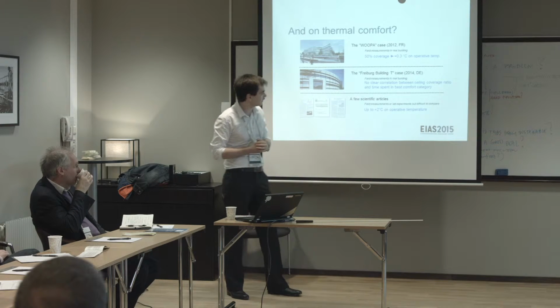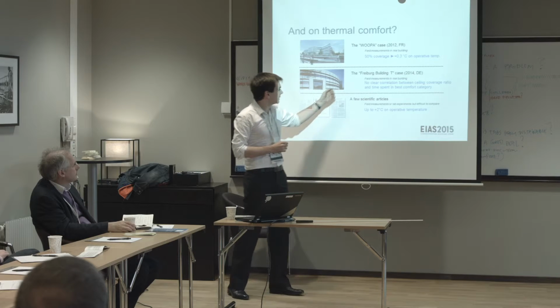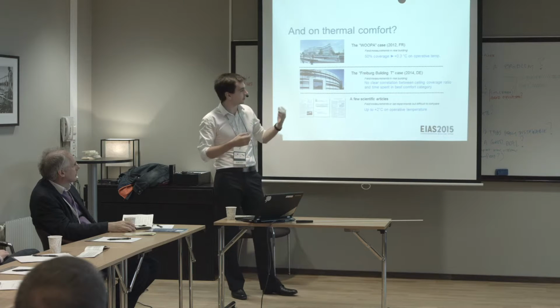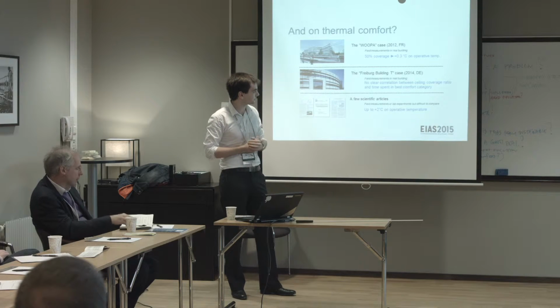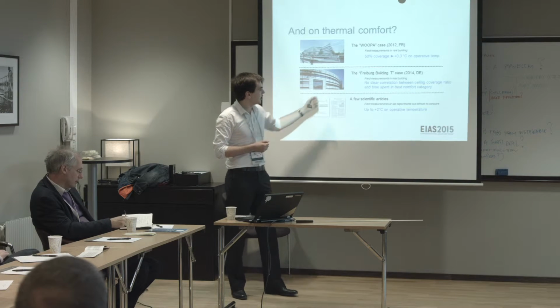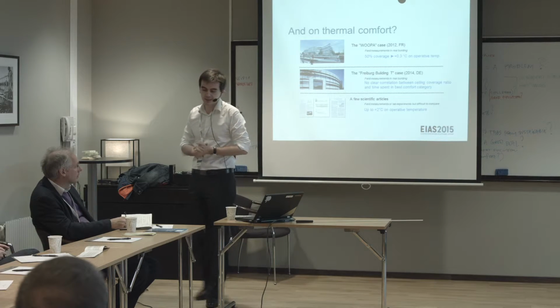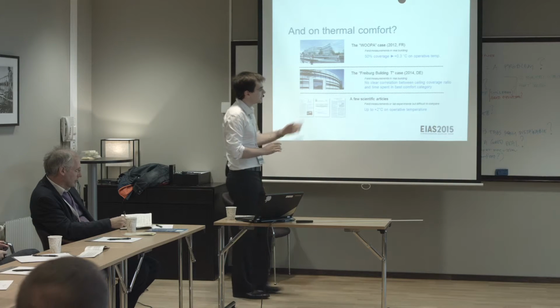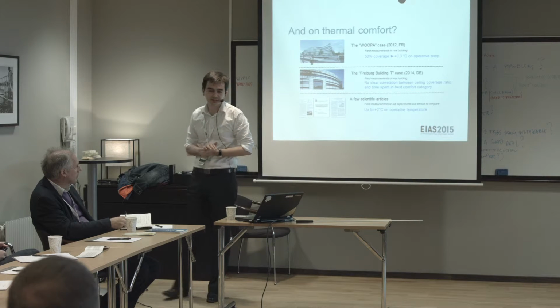in the Freiburg building T. It's in Germany. In this building, we installed more rooms with sound absorbers and more rooms without any sound absorbers, and we compared, and we collaborated with the Fraunhofer Institute. What we saw is that here there is no clear correlation between the ceiling coverage ratio and the time spent in the best comfort category as defined by thermal comfort standards.